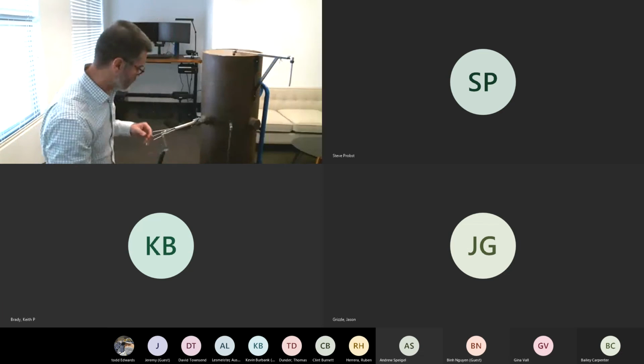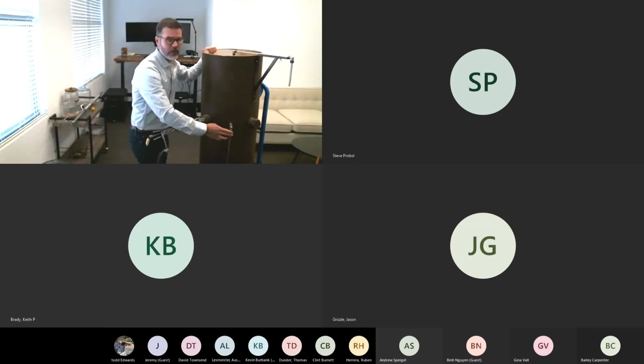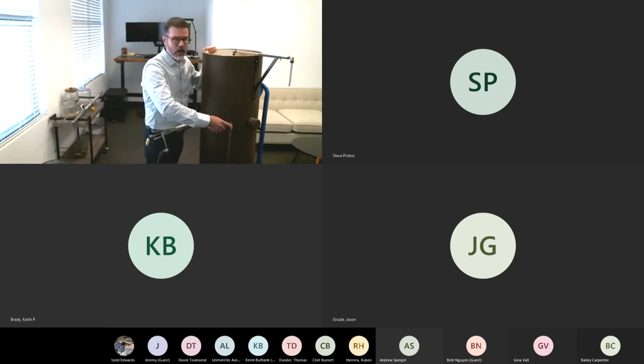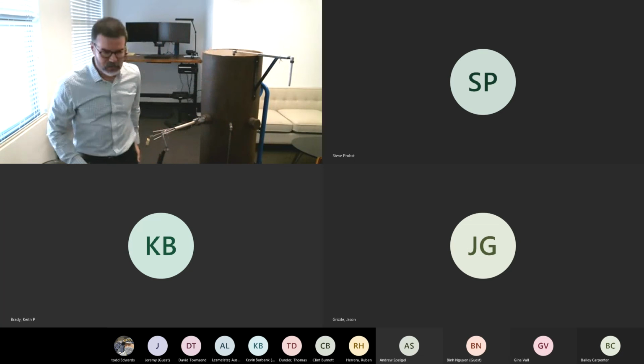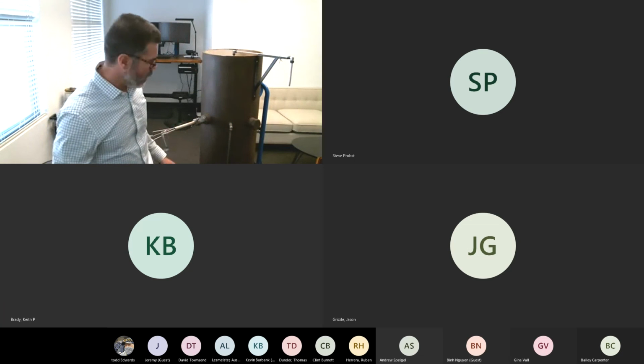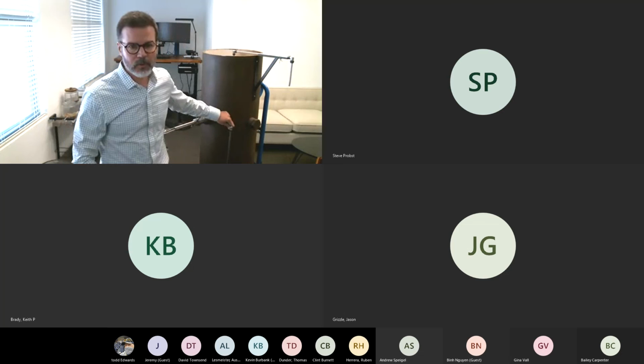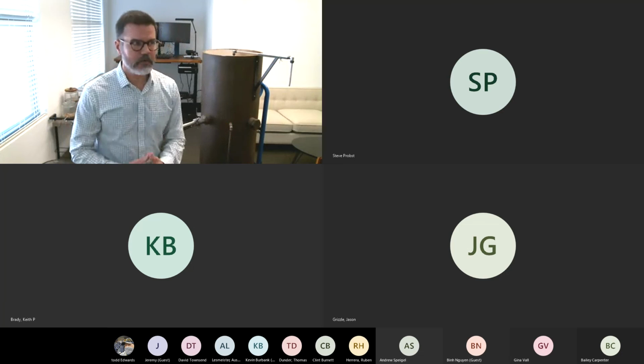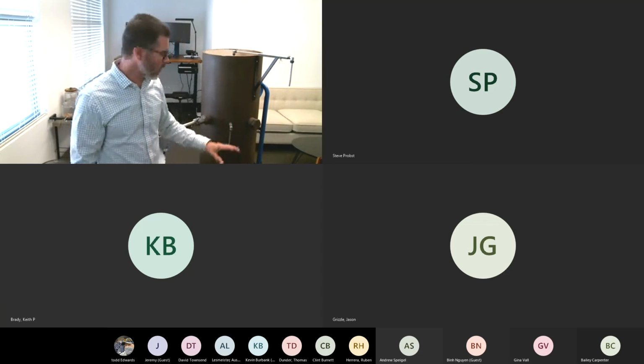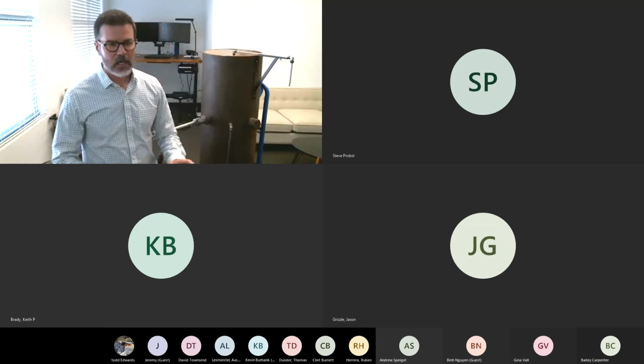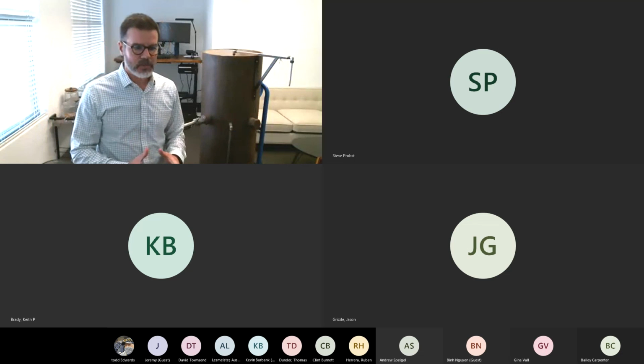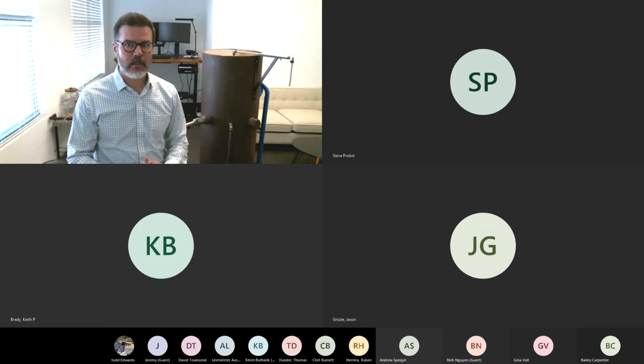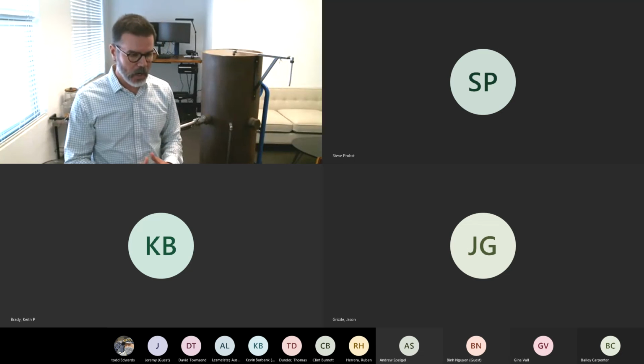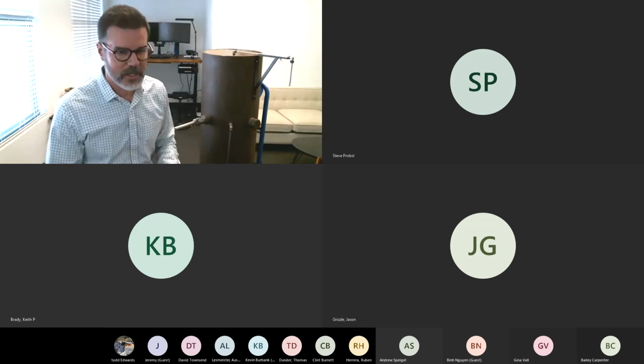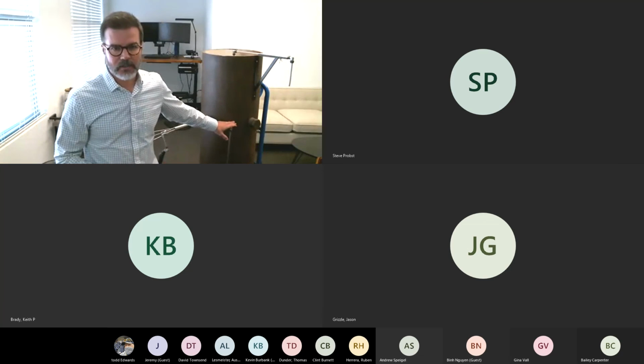Another thing that we commonly see, and it may be sort of difficult here, but right here is what's referred to as a drop-down tubing. And so a lot of operators will put these on their stacks. A lot of compressor rental companies will have these tied into the stacks. And they use these for the purposes of doing their periodic or quarterly testing, using portable analyzers.